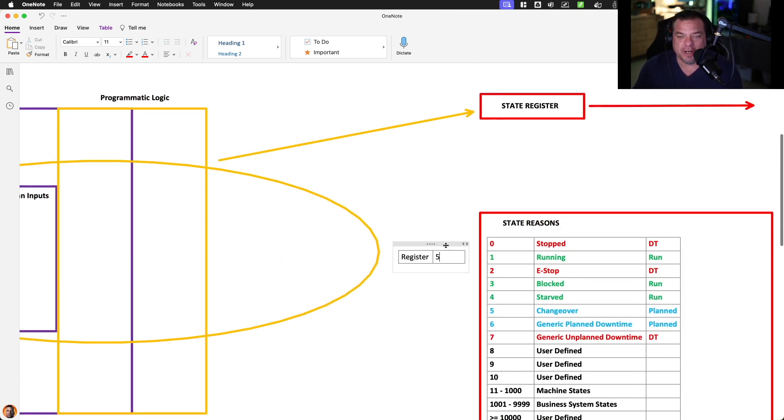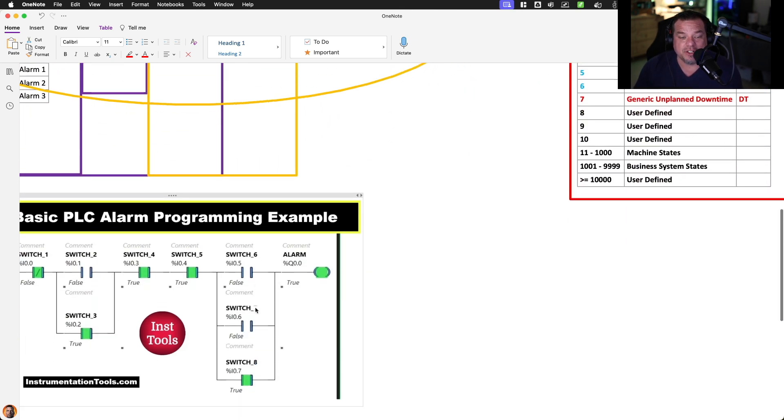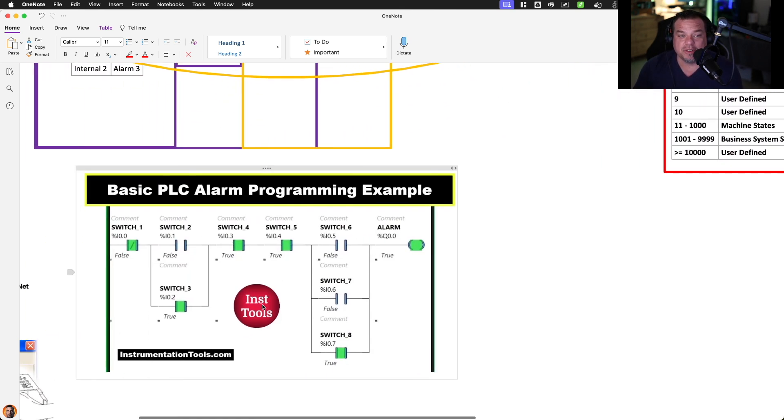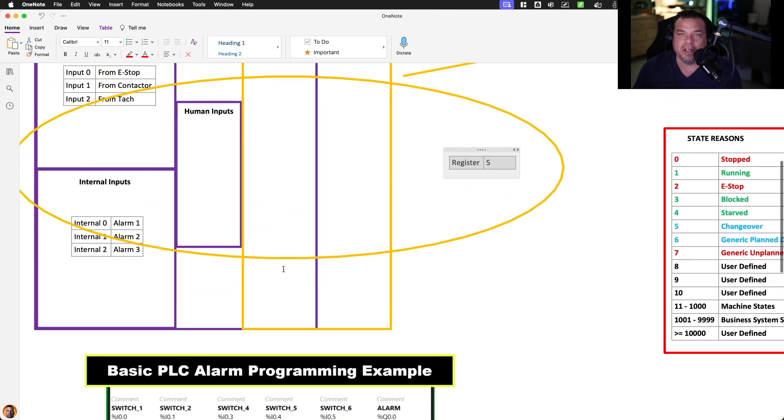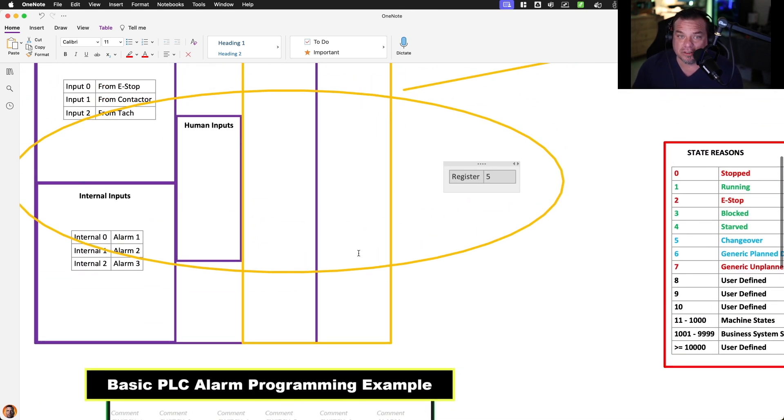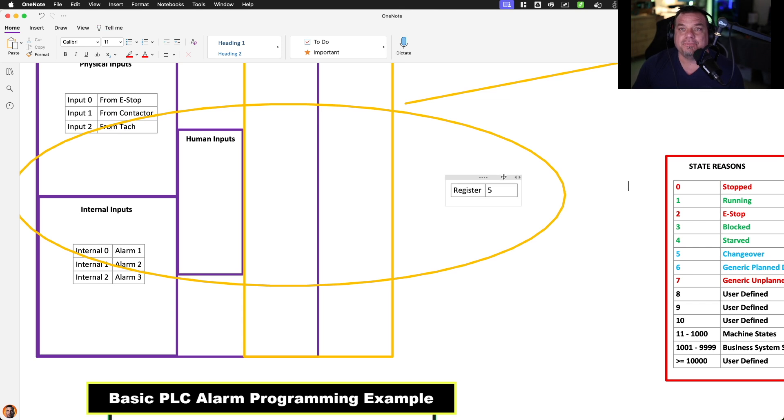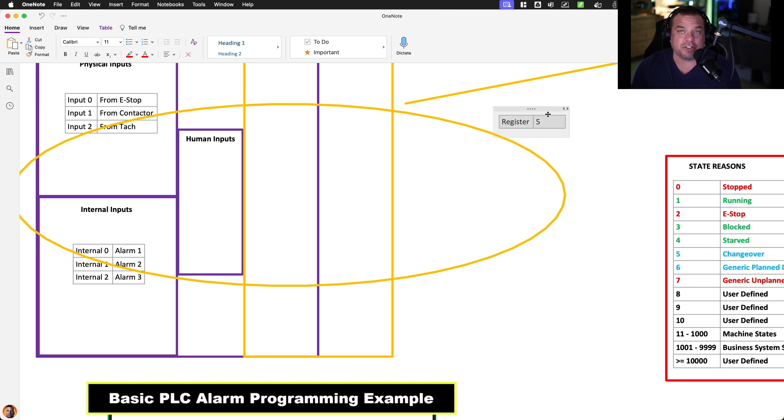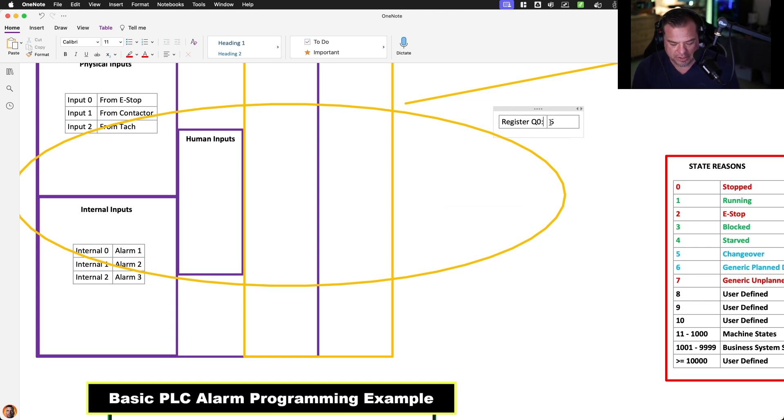So what we do is we generate a status register using logic. Sometimes that logic is internal to the PLC. We may write ladder logic similar to this that creates a status register coming out. In a perfect world, in your minimum technical requirements, you are sending that specification to your machine builder, and the machine builder is shipping the machine with this register. So they give you, hey, the register is located at Q. That's internal input. It'll be internal input zero, and it'll be at, you know, say 16.